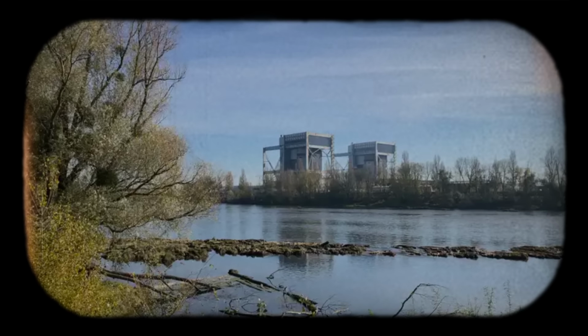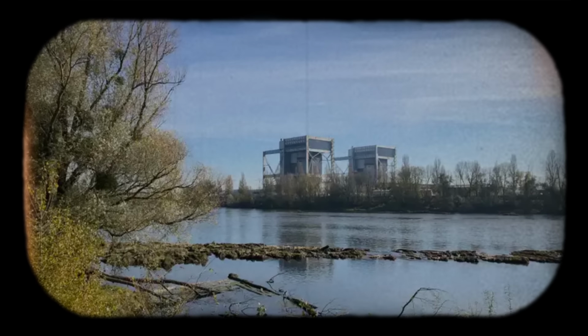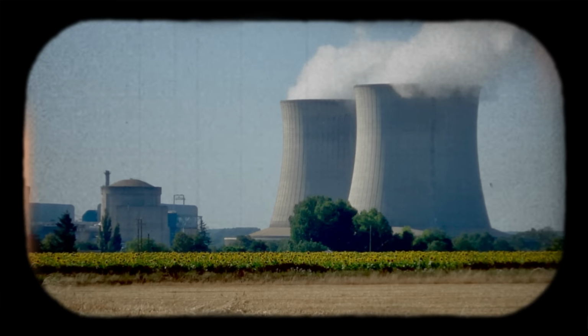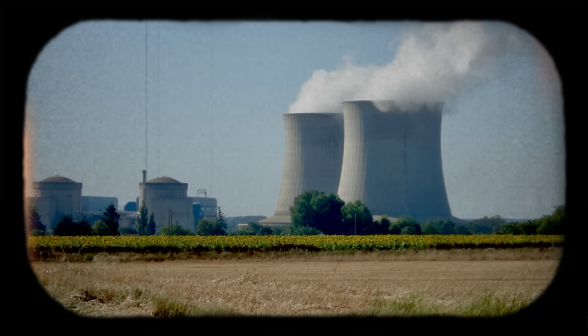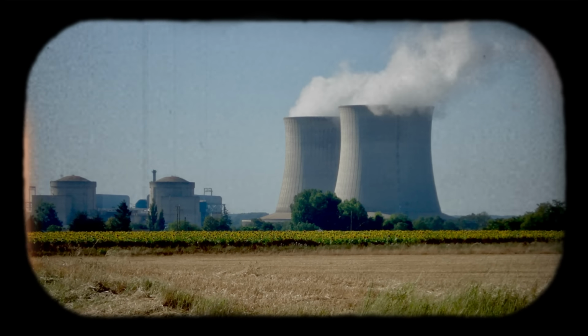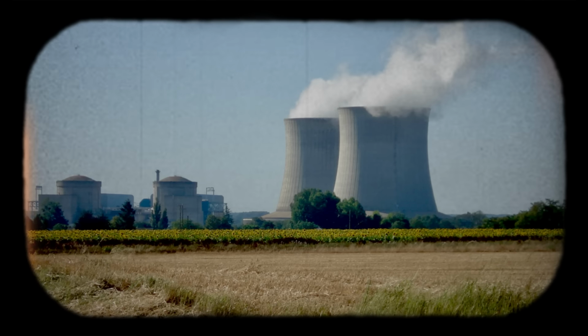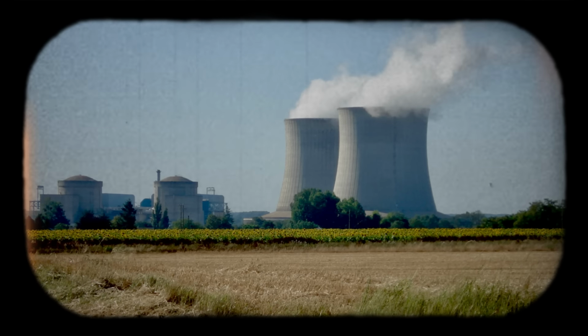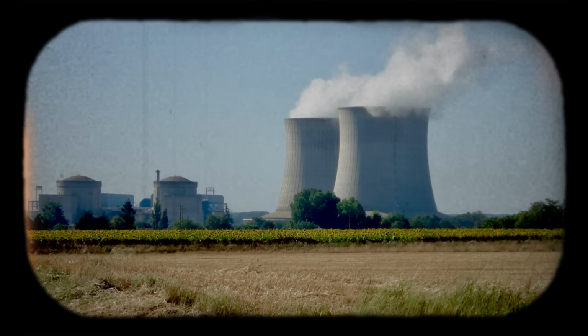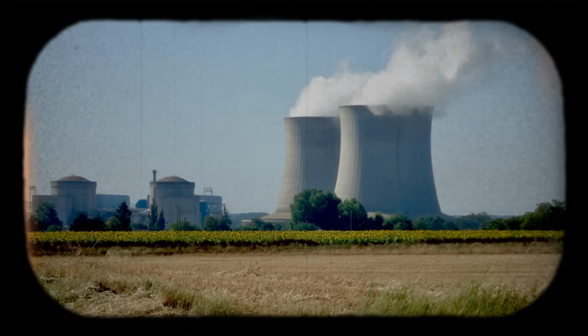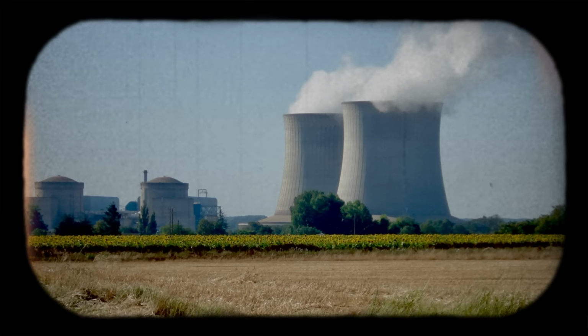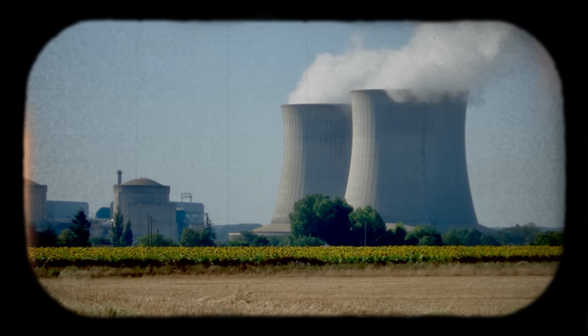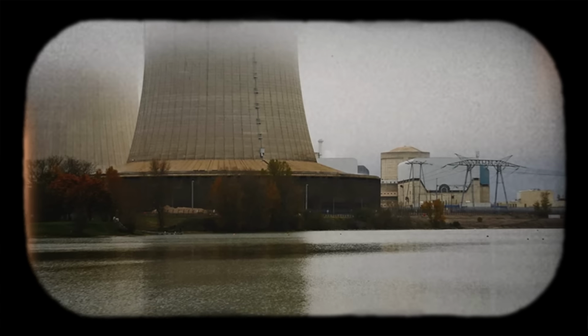Inside the blocked channel, physics dictates the outcome. Fresh natural uranium fuel elements continue fissioning at the power level commanded by reactor control systems. Neutron flux, control rod position, and coolant temperature set the local fission rate. Nothing in the core's neutronics changes when the flow restrictor enters the channel. The fuel continues generating heat at design intensity. Only the cooling has changed. Carbon dioxide flow drops to approximately 1/4 of design. Heat removal falls proportionally.